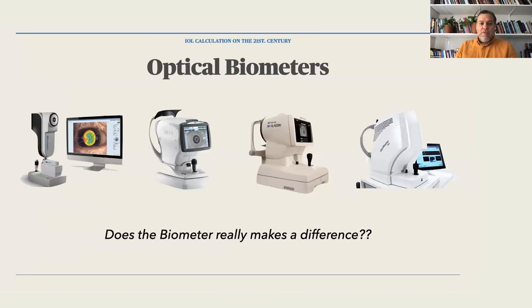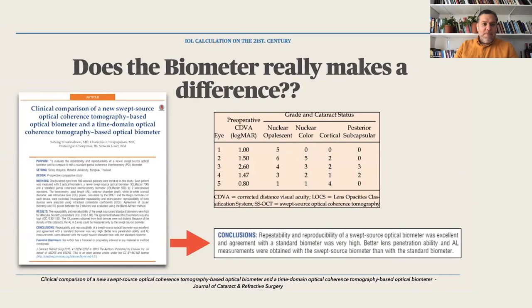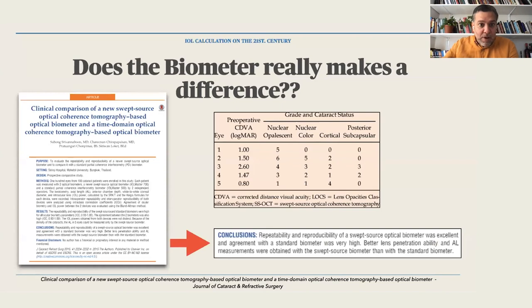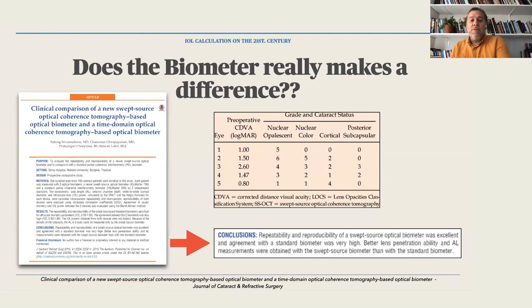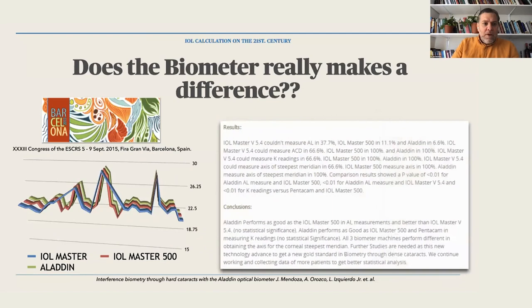So let's talk about optical biometers — does the biometer really make a difference? Reviewing studies, here's one comparing a new swept-source optical coherence tomography biometer with standard optical biometers. The conclusions were that the repeatability and reproducibility of the swept-source optical biometer was excellent, and it agreed with the standard biometer with very high agreement.